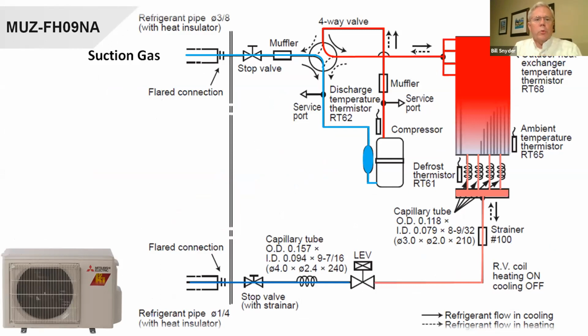Okay, this is an MUZFH. This is a hyperheat, but it does not have that third pipe. Don't need it on this unit. We come out of the compressor. We have a discharge temperature thermistor, a muffler, and a service port in there, through the reversing valve to the outdoor coil. We have an entering and leaving thermistor, in this case what we may call a defrost thermistor, and an outdoor ambient air thermistor. We have some cap tubes, a kind of distributor combination of cap tubes that get rid of some pulsation and keep the pressures up.